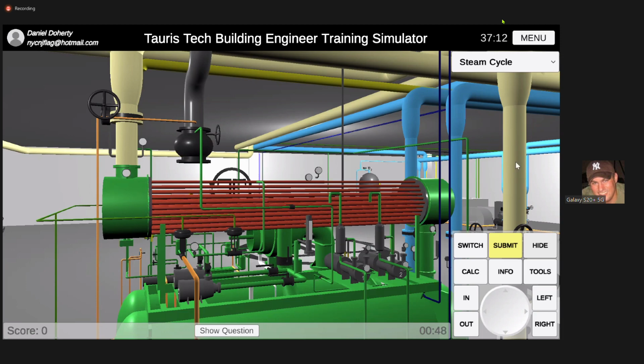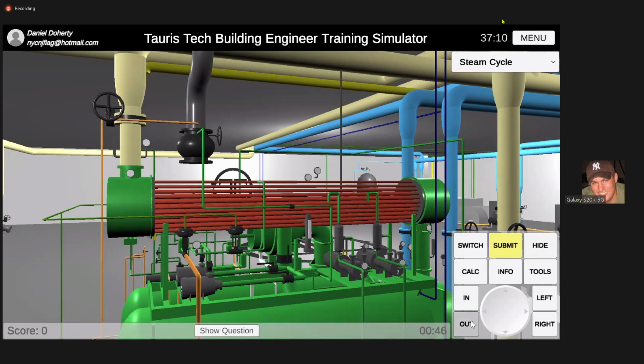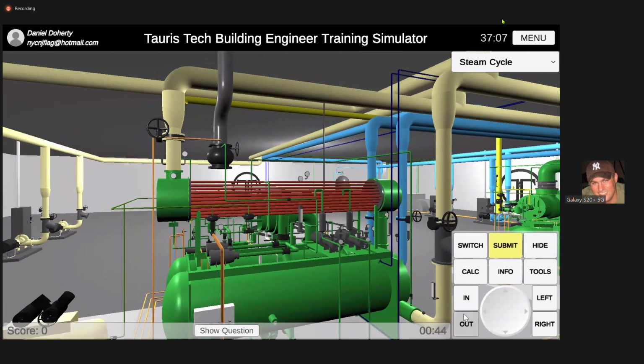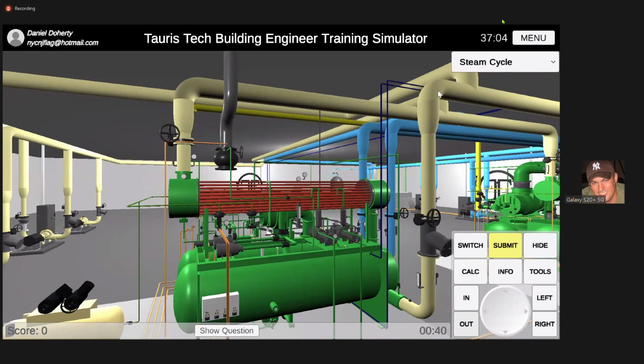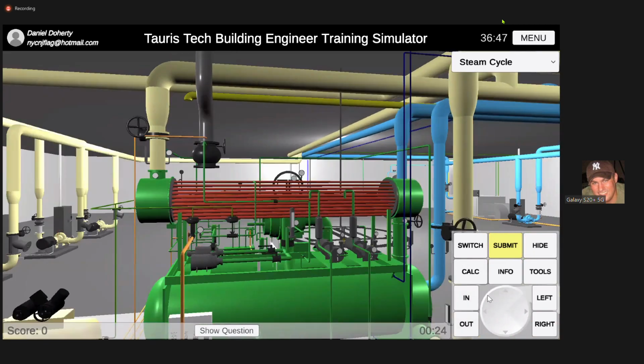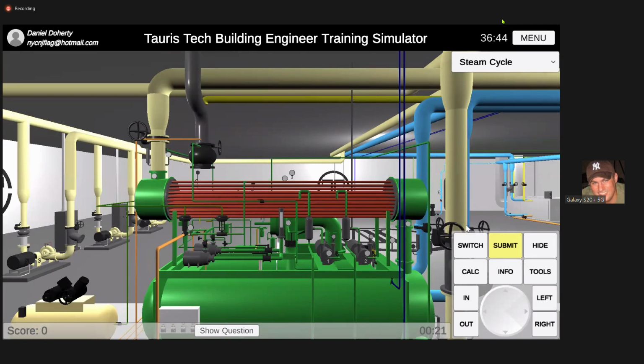towers, right? The cooling water from the cooling towers, that water's coming back down, and it's going into your condenser, right? That's condenser water, and it's making one pass, and it's making another pass. And then from there, it comes up this pipe right here. See that pipe right there? That same water that's in this line goes through the condenser, goes here, and then comes up here, and then that water is going through these pipes. And then it returns to the tower this way, out here.